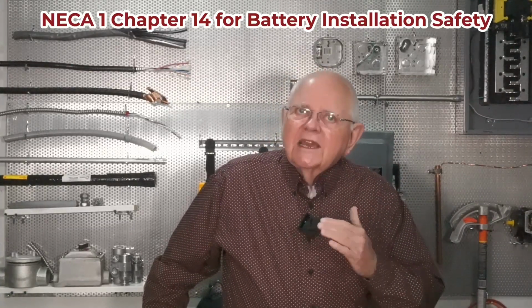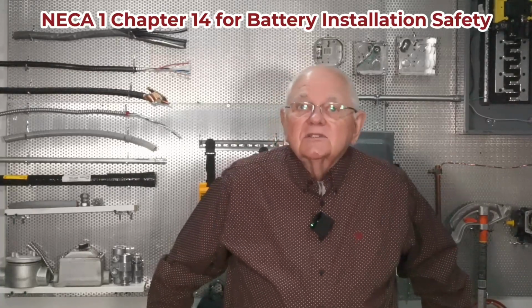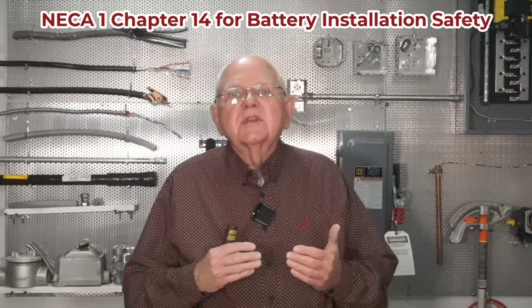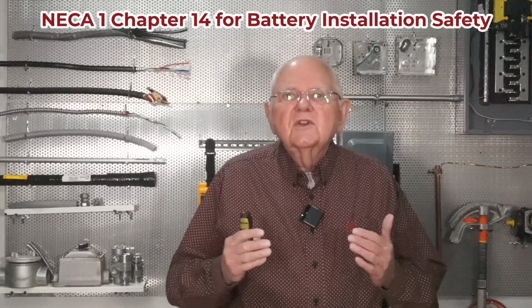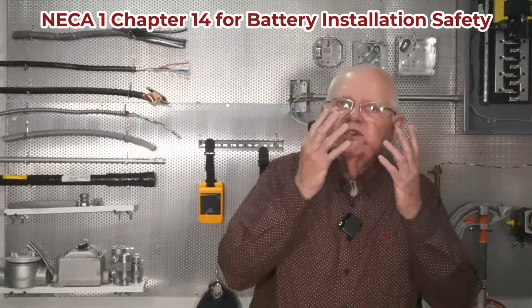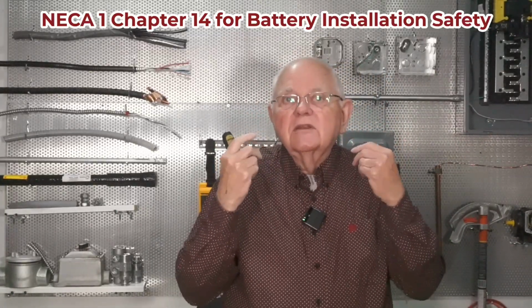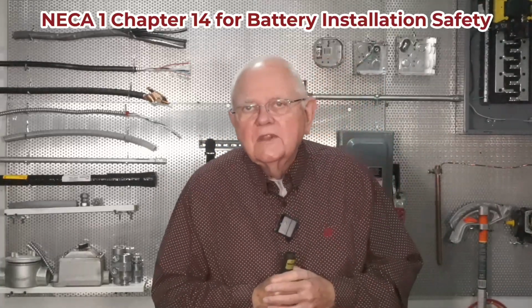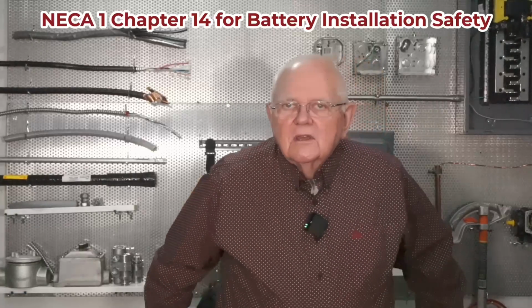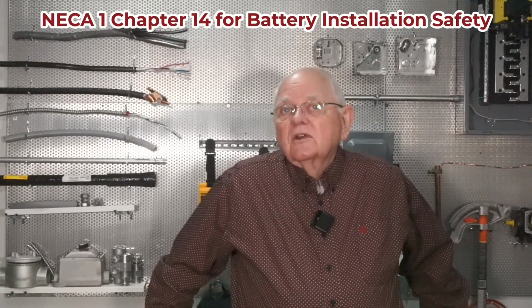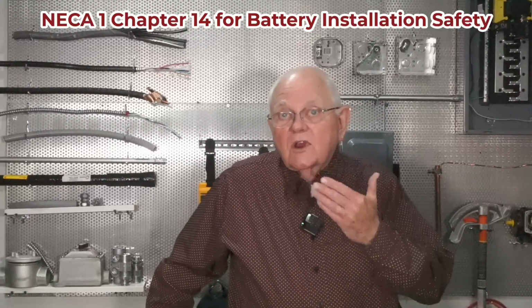So the NEIS standard addresses that. It talks about cell voltage. It talks about PPE. Bottom line, if I'm going to wear PPE working in a battery room, dress for the most prevalent hazard. People say, well, do I have to wear an arc-rated face shield? Well, think about what you're doing. I don't want acid, and that's the most prevalent thing that's probably going to happen if it's a wet cell, a lead acid cell. I don't want acid to get on my face. So if I'm adding some water or acid into that battery, I want to make sure that I'm protected from that most prevalent hazard.